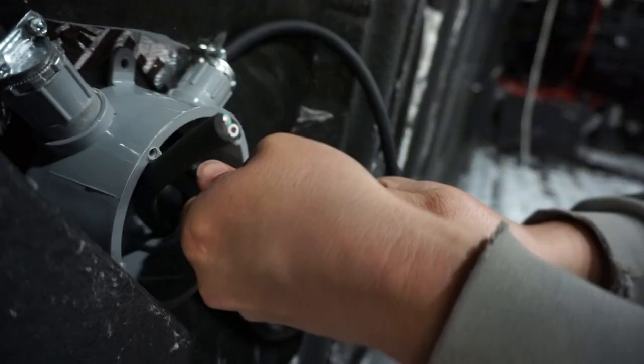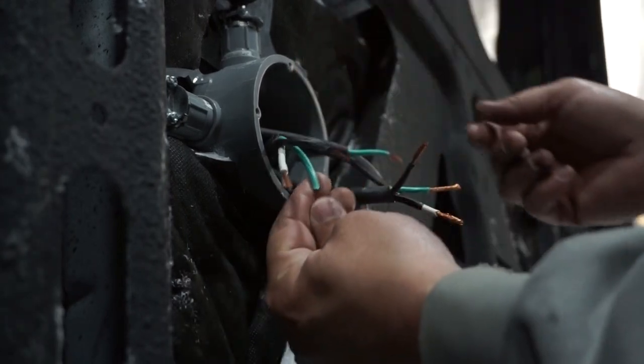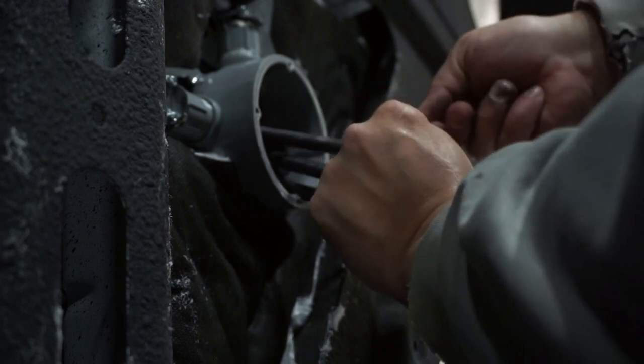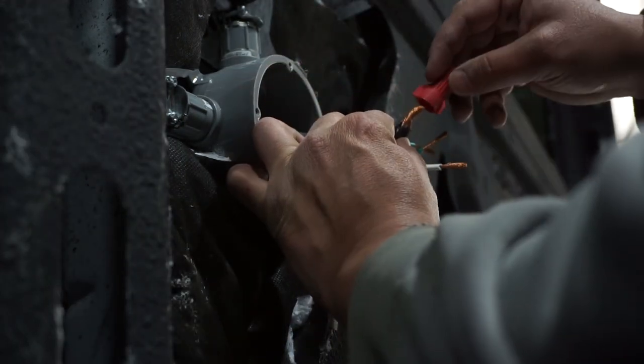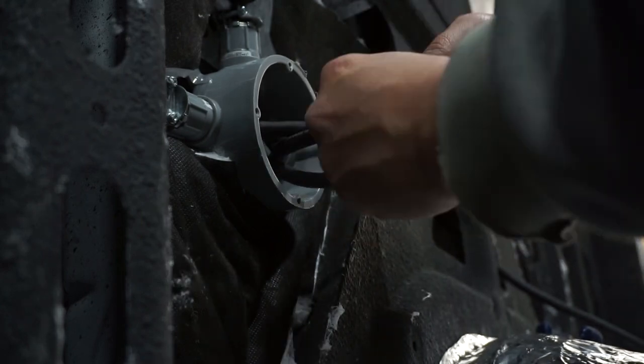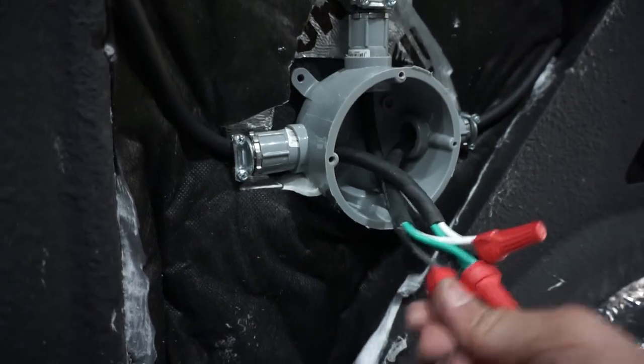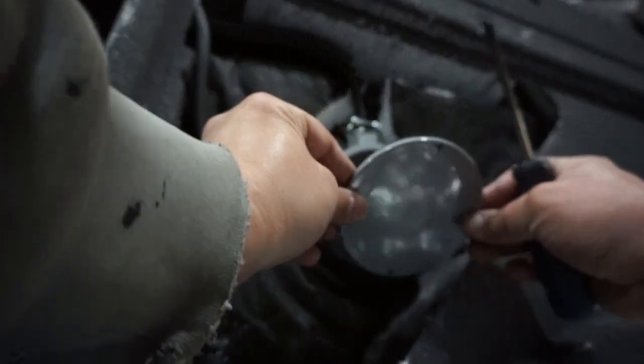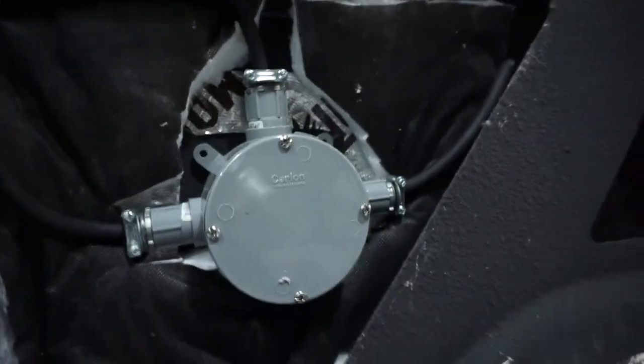With all three wires in the box, we strip back the sheathing, strip back the individual wires, match all the blacks, twist them together, then take one of our wire connectors and twist it over top of all three black wires. Repeat that for the greens and for the whites. Once they're nice and tight and nothing's coming off, she's ready to go back together — just push the wires into place and put the cap on.